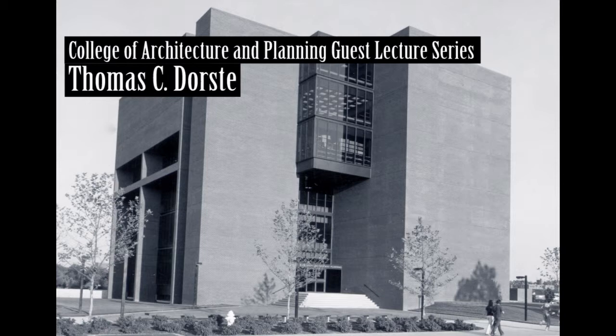We used to pressurize buildings pretty heavily so that all the infiltration was exfiltration and not infiltration. And now we're trying to size that so it's just barely positive pressure by cross-controlling supply fans in a variable volume system with the return air fan, with a static sensor in the ductwork, so that when any room shuts down, the static sensor senses the change in pressure and immediately shuts down both fans to maintain a very narrow difference between supply and exhaust, just enough to handle a situation. This is an energy saver.